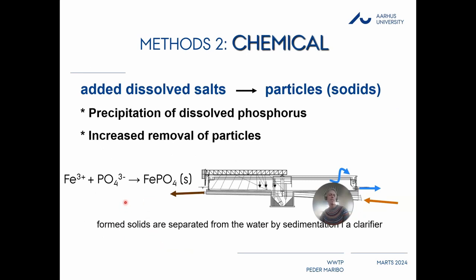Mechanical treatment can be combined with chemical treatment. One typical chemical element is adding metal salts — iron or aluminum. These metal salts react with dissolved phosphorus in the water and form a solid precipitate — for instance a phosphorus-iron precipitate — that becomes an integrated part of the sludge. We can then separate it out from the water. When we remove a little excess sludge every day from the plant, we remove phosphorus from the system this way. The key is to calculate how much iron to dose and ensure sufficient facilities to achieve separation of the formed particles from the purified water.